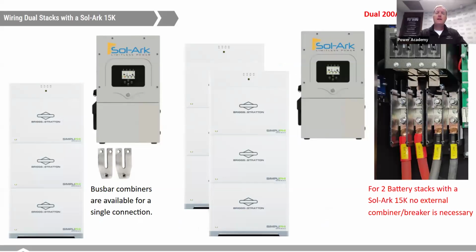Especially the Solar 60K or the Sol-Ark 30K that need those high voltage input ratings. I get this a lot: what's really nice about the Sol-Ark 15K is that it has dual battery inputs. So our battery can discharge at 273 amps DC. And when I say our battery, I mean a stack of three 6.6s, which comes in just under 20 kilowatt hours, a controller on top and a base on bottom.